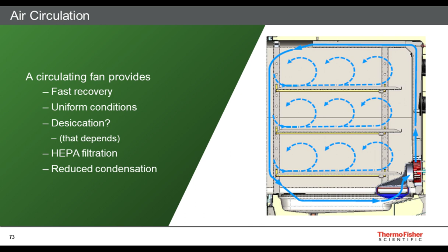So again, some final tips to maintain uniformity and recovery in your incubator that you currently have. Number one, of course, look for an incubator with a circulating fan. Number two, look for data provided by the manufacturer on recovery. Don't just look at specifications. So if you're comparing incubators, everybody has a list of specifications that they meet. So temperature variability, for example. But it's also important to look at data demonstrating how those specifications look.